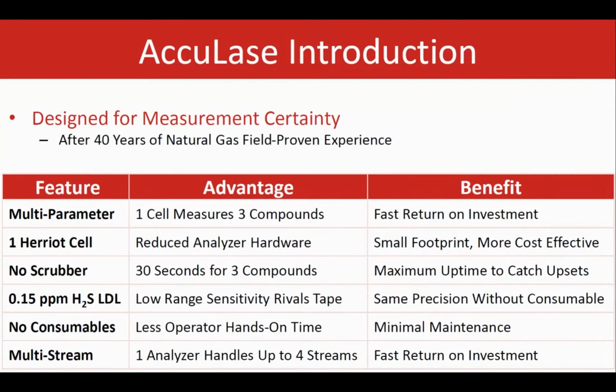There are 40 years of field-proven experience behind designing this analyzer for different applications, for example, the natural gas market. Some of the main features of this analyzer are multi-parameter analysis that can be done with only one single unit. This can go up to 3 species compared to 2, which is typically what we see more present in the market for the other models and brands available. AccuLase only uses one single cell for all 3 measurements, which is again a great advantage because it means a smaller footprint, more cost effective, and less maintenance as well.